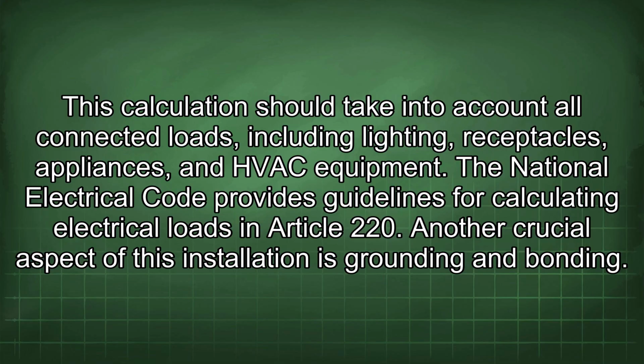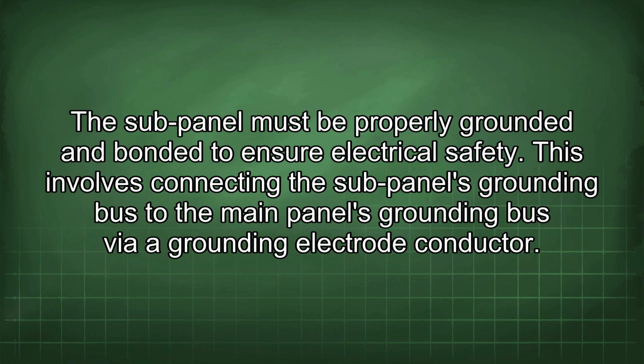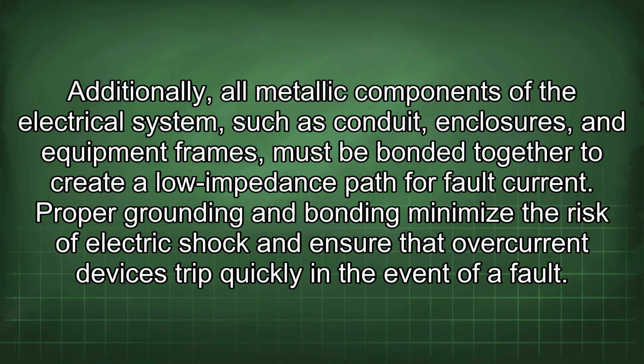Another crucial aspect of this installation is grounding and bonding. The sub-panel must be properly grounded and bonded to ensure electrical safety. This involves connecting the sub-panel's grounding bus to the main panel's grounding bus via a grounding electrode conductor. Additionally, all metallic components of the electrical system, such as conduit, enclosures, and equipment frames, must be bonded together to create a low-impedance path for fault current. Proper grounding and bonding minimize the risk of electric shock and ensure that overcurrent devices trip quickly in the event of a fault.